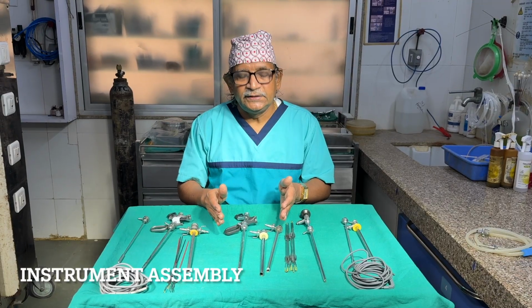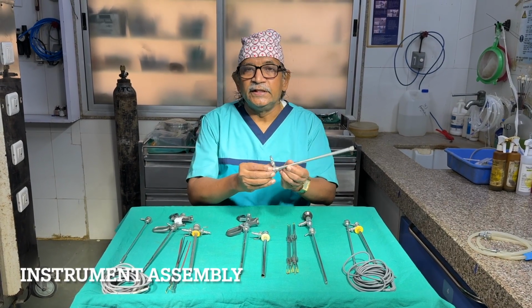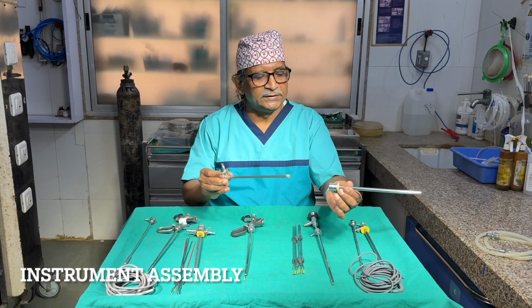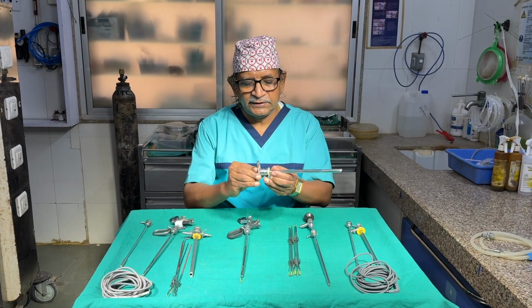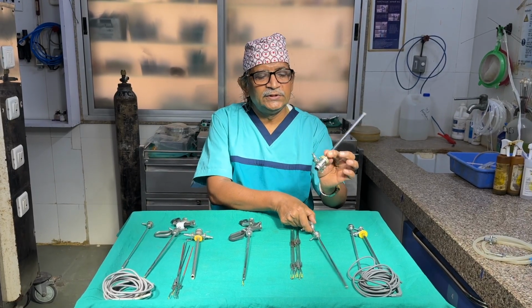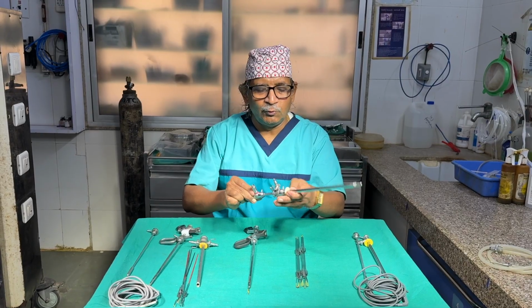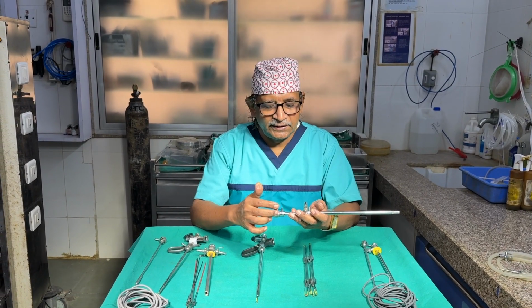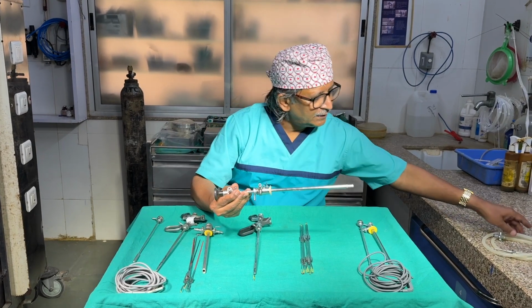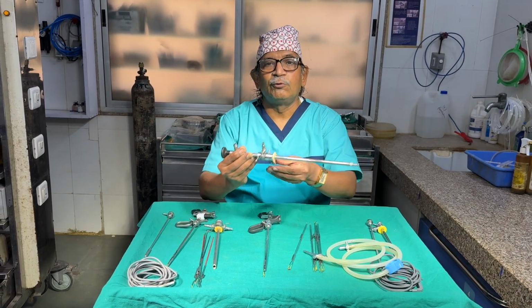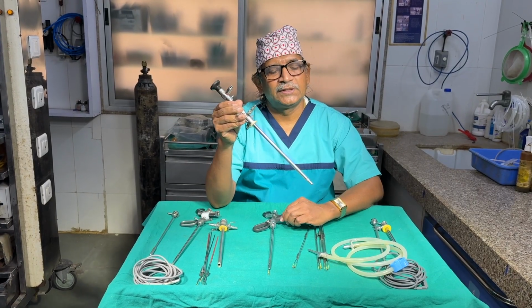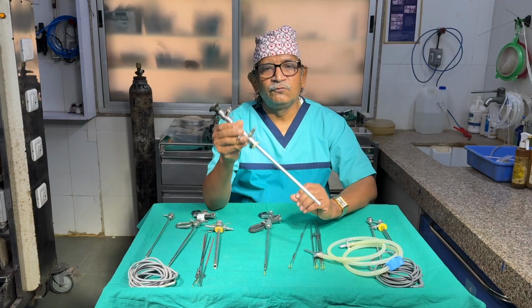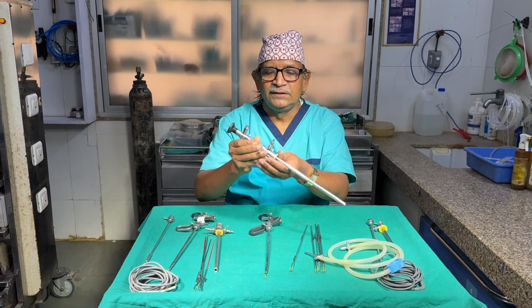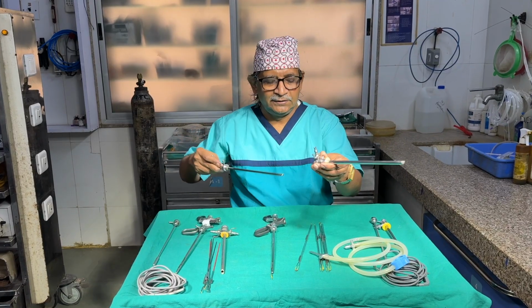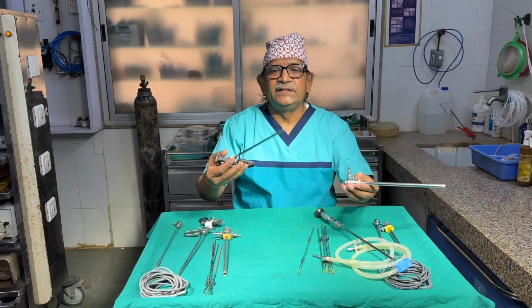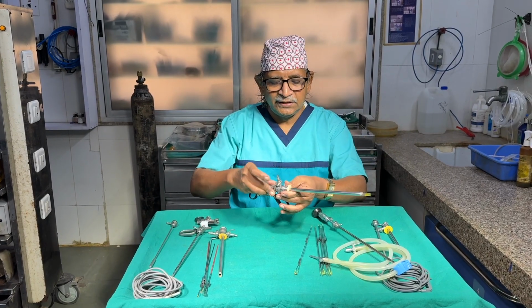Now we will assemble the standard TURP set. This is the inner sheath, this is the outer sheath. You have to match these zeros, put in the inner sheath, and this is locked. Through this assembly, our visual obturator with the telescope will go. Here we will be attaching the light cable, and now this becomes the complete assembly. We will be attaching an inlet tube here, and the outlet tube will be attached here, and this instrument is passed through the urethra under vision. Once we confirm the passage in the bladder, then we remove this visual obturator, and through this we will pass the working element with the telescope.